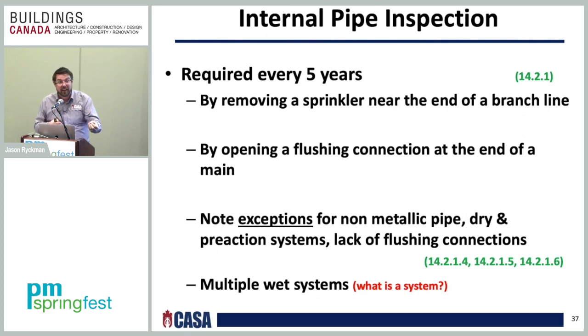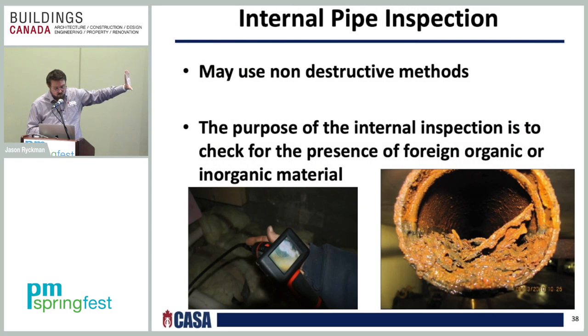Now, if you do find obstructions within the wet system that you are inspecting, then you have to do all of them. So there are some good exceptions to the rule in NFPA 25 which can help you in that aspect. Also, here's just a picture of what you can find within your pipe. That's pipe scaling. A pipe scale like that could be significant. I would consider that significant.